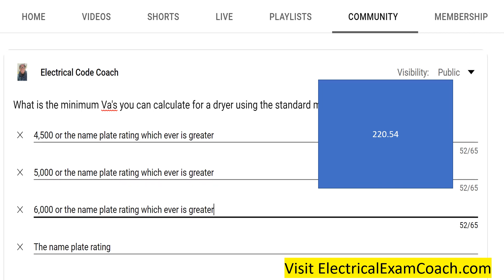There is a demand factor that can be applied using Table 220.54, but before you can even get to Table 220.54, you must understand this part. When we go back to Section 220.54, it lets us know that when we're doing the standard method, we must use 5,000 VA's or 5,000 watts as the minimum, or the nameplate rating, whichever is larger.